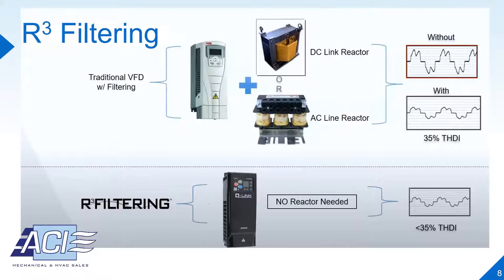Let's now dive a little deeper into R-cubed filtering. Traditionally, with other VFDs, there is a DC-Link reactor or AC-Line reactor to mitigate harmonics. We want to mitigate harmonics because they are wasted energy, cause excess heat, and can cause equipment to malfunction. When the DC-Link reactor or AC-Line reactor is used, there is 35% harmonic distortion. The Q-Link has built-in technology called R-cubed filtering, which is a sophisticated filtering algorithm that mitigates harmonics the same way as the DC-Link or AC-Line reactor, except it gives less than 35% total harmonic distortion without an external reactor. R-cubed filtering can be thought of as having a 3-5% line reactor built right into the drive.